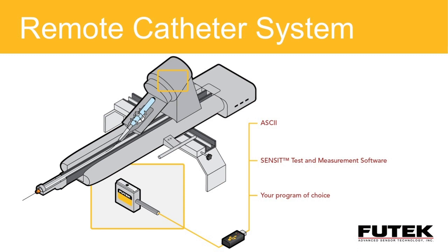In these applications, it's very important to be able to control the catheter as the surgeon inserts the catheter into the patient. This process of controlling the direction and motion of the catheter is done by tension controls of control wires, and the force measuring those wires is done with our LSB 200.